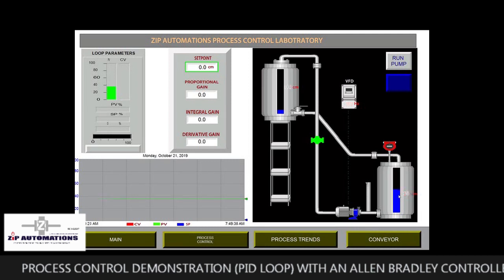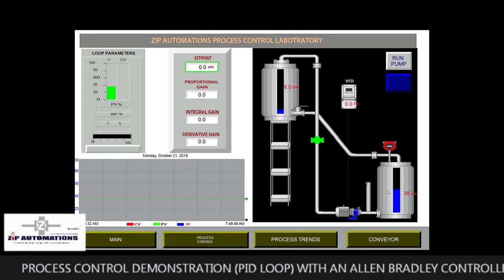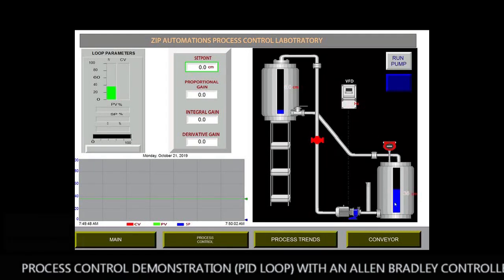Let's assume our set point is 22cm. What that means is we are trying to keep the water level in this tank at 22cm. So if the water goes above 22cm, the program is going to ramp up the VFD to drain water from this tank back to our set point of 22cm. And if the water level goes below our set point, the program is going to ramp down the VFD, attempting to shut it down.